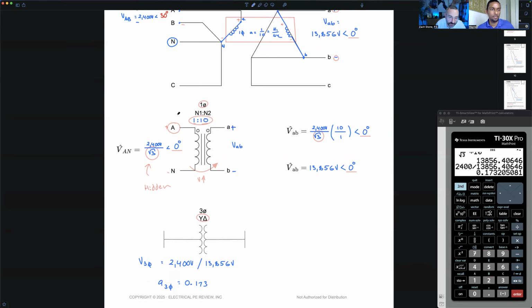This is the single phase turns ratio. And then we could figure out the single phase voltage ratio of each transformer to compare: it would be 2400 divided by the square root of 3, compared to that times 10.